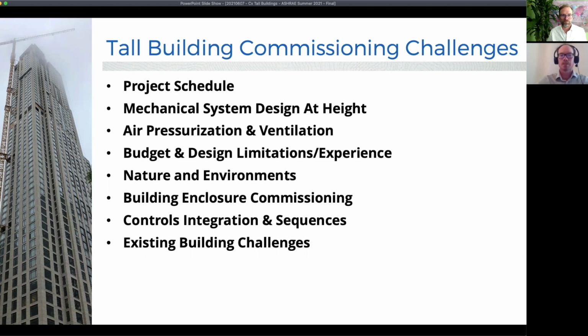The next is controls integration and sequences. We have to manage stack effect. We have to mitigate it, and we're going to do that through a bunch of different variables. But ultimately, on the HVAC side, through the controls or automation system, and some complicated sequences, right? So to have that variability and have that air control is hugely important in mitigating stack effect. And then we're going to talk about some of the existing building issues and challenges that we've seen. Obviously, if we're working from new construction and have a commissioning plan and process in place, then that's definitely going to be different than walking into an existing building and trying to root cause some of these issues and put together a practical mitigation plan and implement that in the real world.